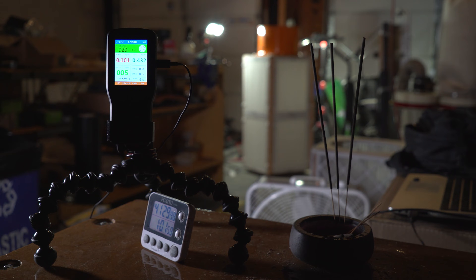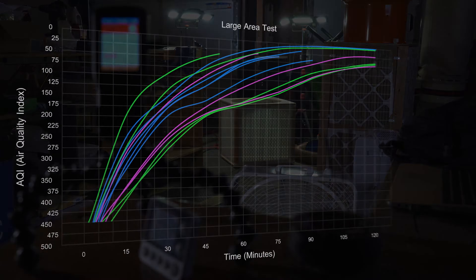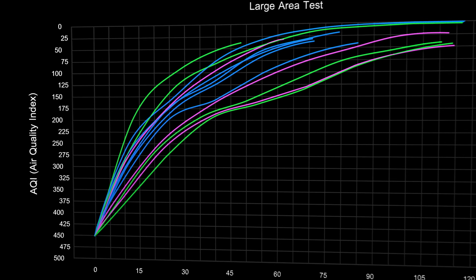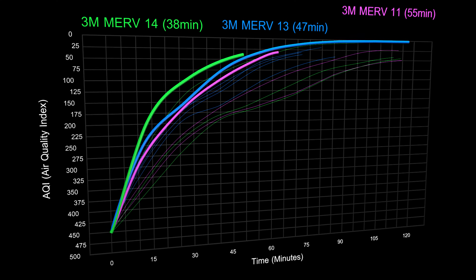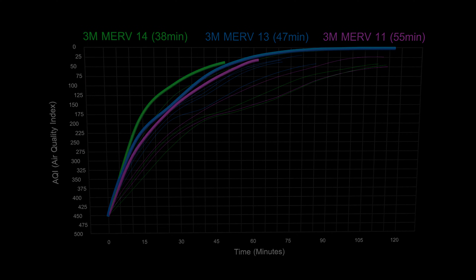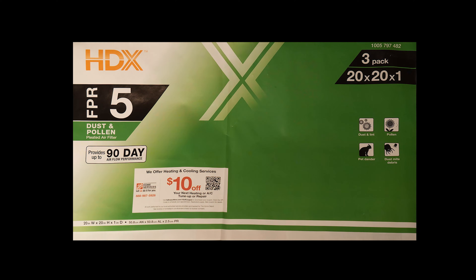The bulk of my tests were centered on the 4-filter design, but the results also apply to your home's HVAC system. Here is how long it took these 20 by 20 inch filters to clean the air. Despite the more restrictive nature of the 3M MERV 14 filter, it performed best overall. In fact, all of the 3M filters performed best in their respective MERV categories. The MERV system is used to classify how well an air filter removes small particles from the air. If you are concerned about air quality, I do not recommend anything under a MERV 11.